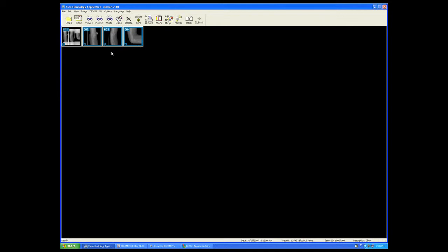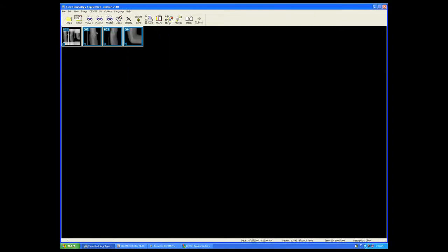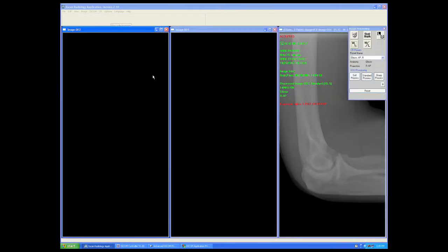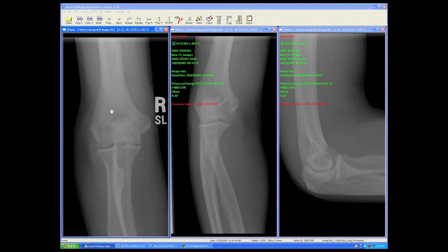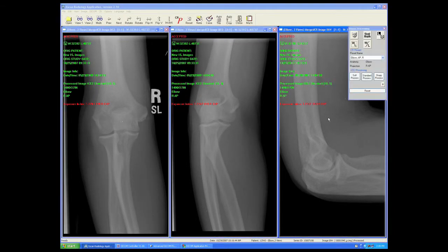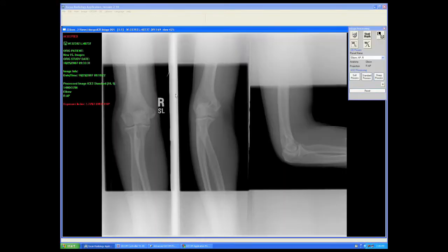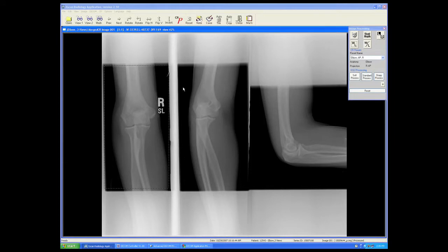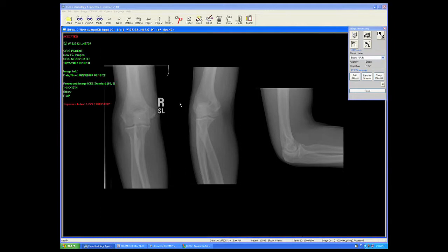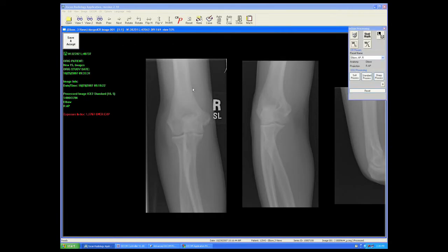all three of those images that can be viewed by the radiologist as three separate images on one screen with the View Multi button. Now this will allow the radiologist or the reviewing physician to window, level, magnify, and zoom on the individual images as opposed to viewing the 3-on-1 with the mask. Where when I window and level on one image, it's actually happening to all three.